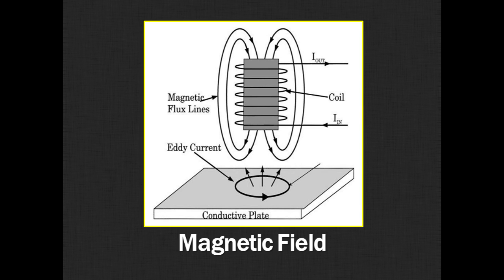As the target gets closer to the probe there's more of the field being created in the target. It's creating more of a counteracting force and what happens is it affects the loading on the probe and the electronics which establish an oscillation. They establish an oscillation at a certain peak-to-peak level and what happens is as that target material gets closer to the probe it starts to take more energy out of that oscillation and shrinks the peak-to-peak signal, the oscillating signal. So we can also think of this as stealing energy if you will. The electronics is only putting a certain amount of energy into this probe so with no permeable or conductive material nearby it will establish that same peak-to-peak level and when the permeable material comes in the path then it shrinks down.